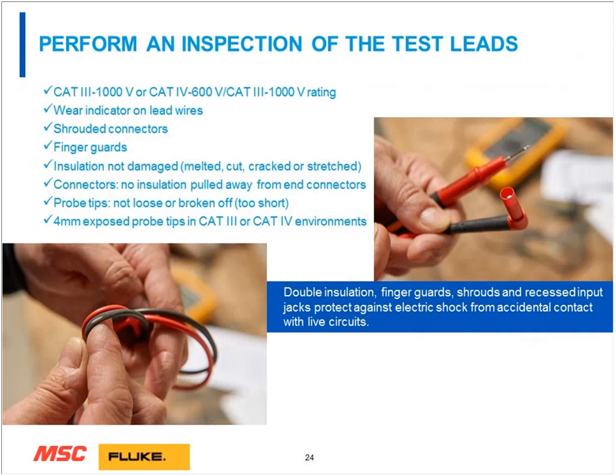Perform an inspection of the test leads. Some of the test leads are actually shot with multiple layers of coatings. So there's a white coating under the black or under the red coating on the outside. Take a look through, make sure they're not cut, they're not damaged in any way. Take a look at the flexible restraints, the double insulation, the finger guards. Make sure that the test leads are in good working order. Test leads are an inexpensive part to any meter compared to your safety. I recommend replacing them at least once a year.